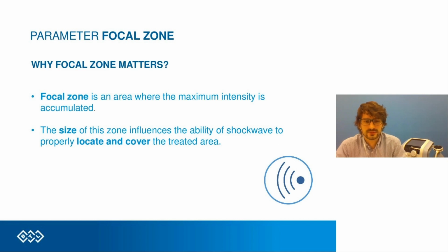And then another parameter which is specific for the focus shockwave is something that we call focus zone, and this is basically how large the area inside of the tissue is that has the highest intensity. So this is important because some devices have a focal zone or focal point that is very small, and it's hard to locate, for example, the tendon or calcification. So that is why, when the devices are compared, the bigger focal zones are more user friendly, because it's easier to target and affect the desired tissue.